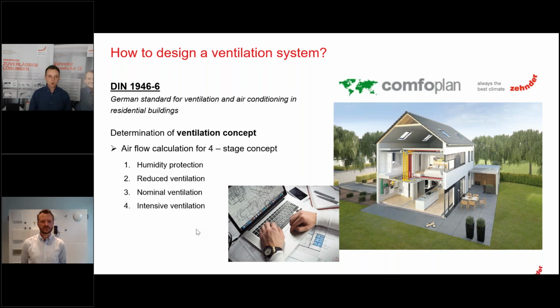When you begin such a project, you need to determine at the beginning whether a ventilation system is necessary at all. By typing in some building parameters, the tool calculates the results. So you need to type in which building type you have. So is it a single family house, multi-family house, or row house, and so on. What is the external wind influence? What is the insulation level and the air tightness, of course, the energy standard, and also how many people are living in that building, because it is recommended to calculate at least 30 cubic meters per hour per person.